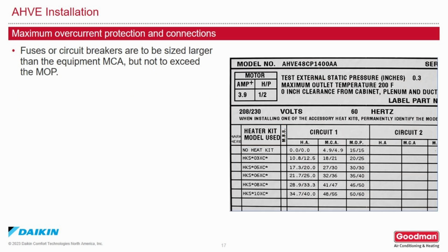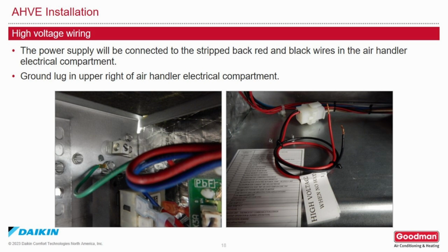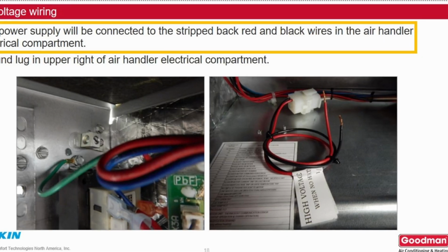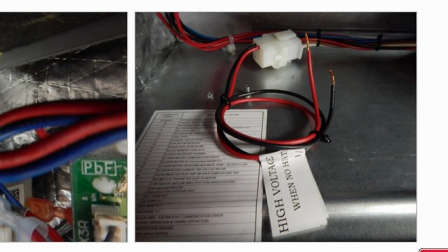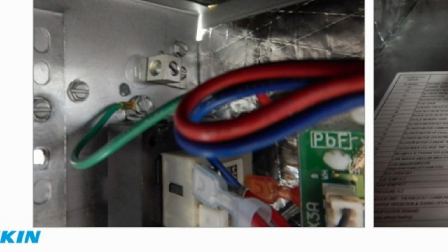Fuses and circuit breakers should be sized larger than the equipment minimum circuit ampacity, but do not exceed the maximum overcurrent protection. This information can also be found on the unit data tag. For high voltage wiring, the power supply will be connected to the stripped red and black wires in the air handler electrical compartment. Ground lug is in the upper right-hand corner of the electrical compartment.